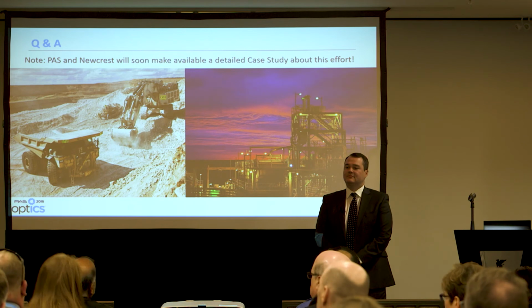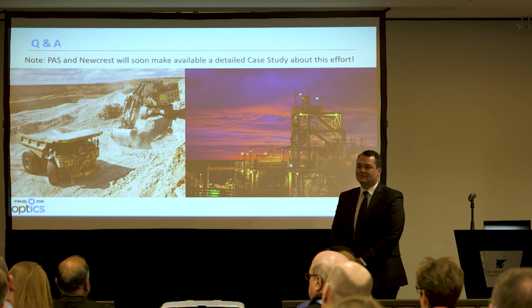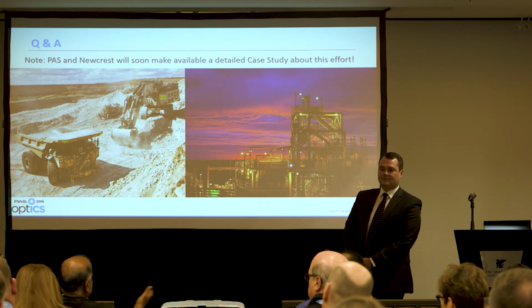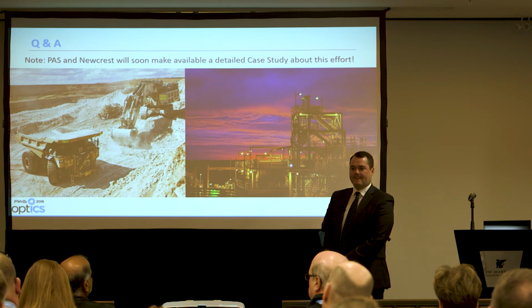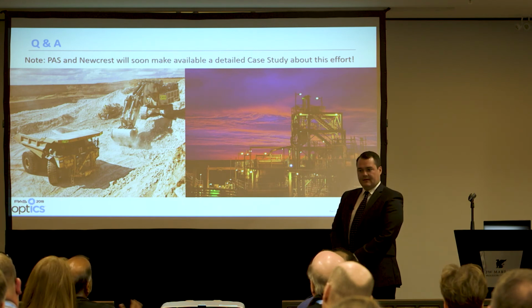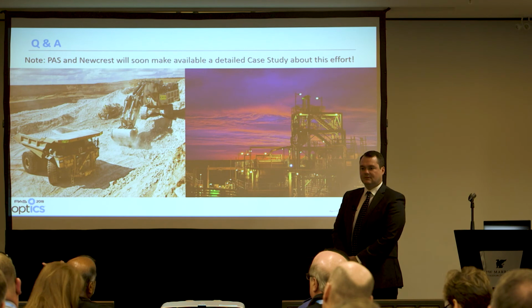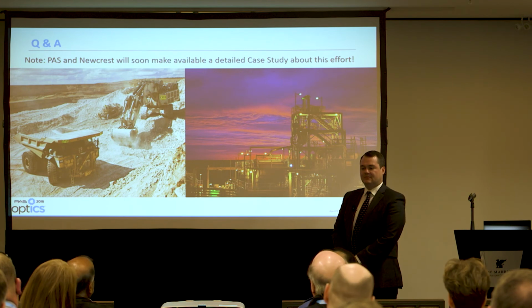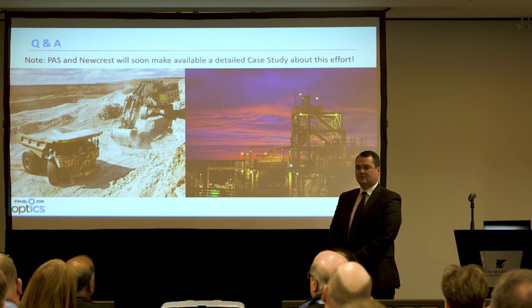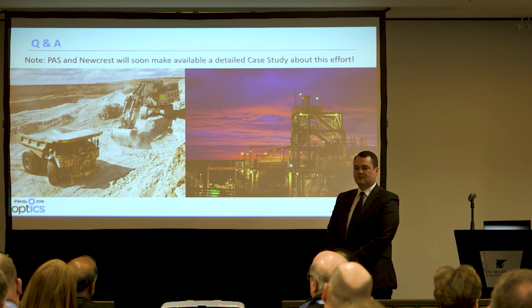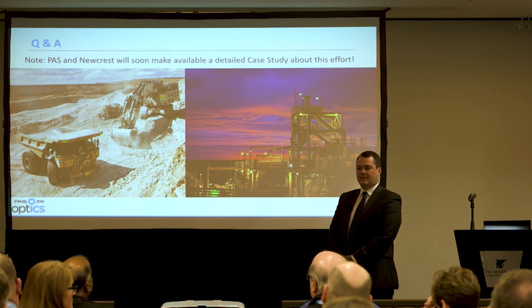Did you also implement state-based alarm suppression, like when a big piece of equipment is not working you can suppress all the alarms associated with that equipment? If you're correctly configured with the DCS regarding hierarchy of plant, yes - you need the equipment level and associate all the alarms to that, and when that equipment is not running or down, turn off all the alarms.